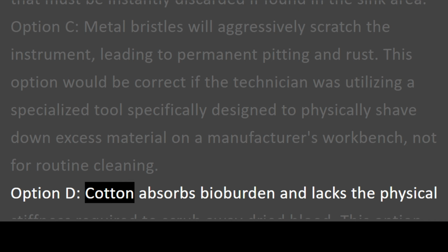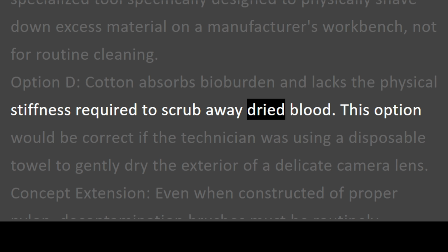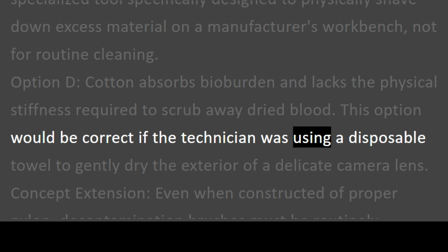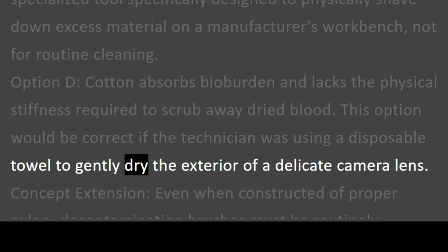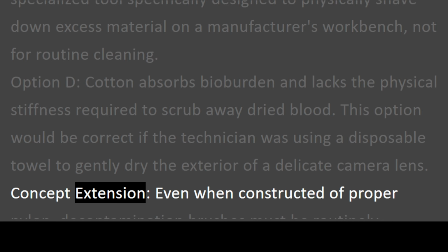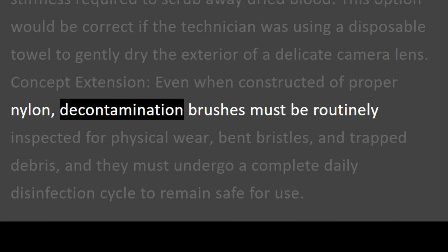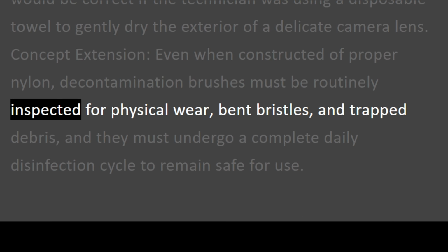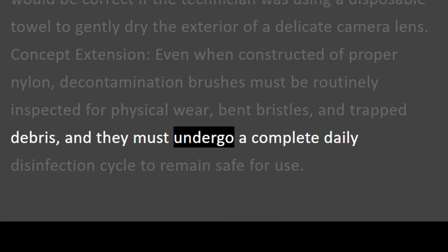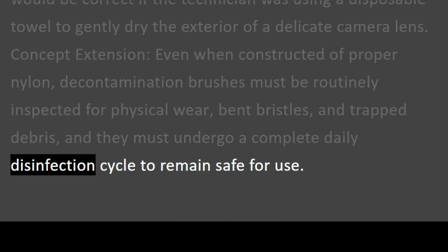Option D. Cotton absorbs bioburden and lacks the physical stiffness required to scrub away dried blood. This option would be correct if the technician was using a disposable towel to gently dry the exterior of a delicate camera lens. Concept extension. Even when constructed of proper nylon, decontamination brushes must be routinely inspected for physical wear, bent bristles, and trapped debris, and they must undergo a complete daily disinfection cycle to remain safe for use.